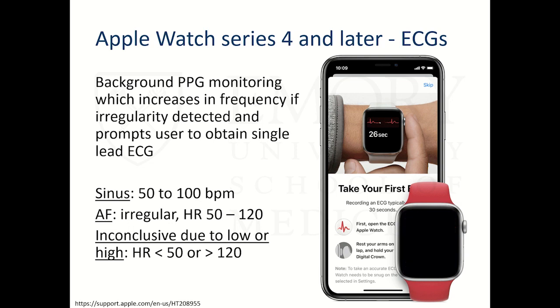Now, it's important to remember that the watch doesn't continuously record an EKG. The ECG is not the primary mode of screening. Even Apple Watches Series 4 and 5 still use PPG. So every couple of hours that an individual wears the watch, the device in the background takes a PPG tracing. If it looks regular, doesn't detect an irregularity, it checks again in a couple of hours. If it detects an irregularity, it increases the frequency of PPG screening to about every 10 or 15 minutes or so. And if over the course of several recordings in a shorter time window, it continues to detect an irregularity, it prompts the individual wearing the watch to say, an irregularity has been detected, you may want to consider obtaining an EKG, and then the person can obtain a 30-second EKG, and that's how it correlates ECG with the PPG screening. But the background operation is still PPG based.